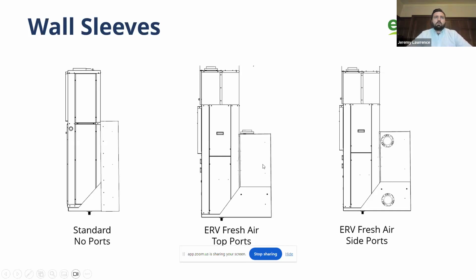And we watch for that as we're looking at projects or quoting, and we'll suggest accessories that may help with that. The only time I've ever seen the unit actually have any sort of frost on it is we did a project, it was Sudbury, I believe, and it was the north-facing side of the building. So in the coldest of the cold periods, there's a possibility that this case could get cold enough that humidity inside the living space would freeze to it. But in that case, we supplied an insulation panel that covers the unit to stop that. The first company has made that consideration, and they have an accessory available to stop it. Yeah, it's extremely rare because of the airflow, it's very rare for frost to build up at all. Perfect. But that is certainly something to look at.